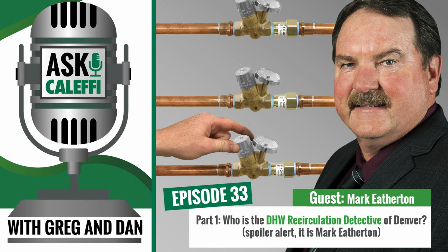A lot of older systems out there are in dire need of help. They were not piped in a manner that is conducive to flow. I think I've seen one system that was actually piped parallel reverse return that didn't require any balancing at all, and it was still running at excess velocity. But most of them are piped parallel direct return. As we all know, water is like my ex-brother-in-law: wet, lazy, and stupid.